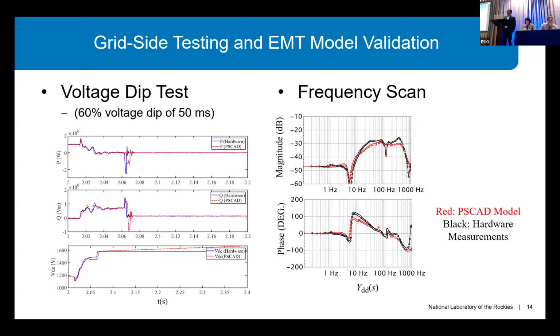And on the right is an impedance scan, where we are looking at the D-axis admittance of an inverter, and comparing the response between the PSCAD model and the actual hardware. We had to go through several iterations on improving the model quality. So here you are seeing textbook type response or matching between model and the actual hardware. But of course, initially the model had some issues that we had to figure out and work with the vendor to address.